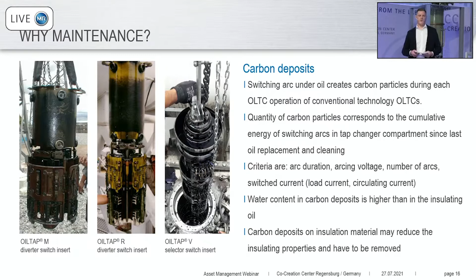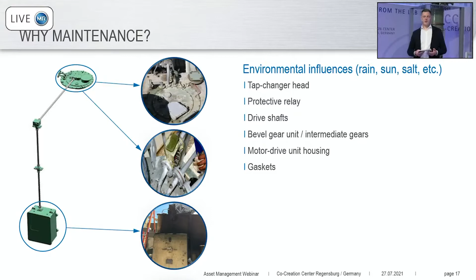Then, of course, we have some environmental influences on the tap changer cover, on the protective relay, drive shaft arrangement, the bevel gear unit, the motor drive unit housing. All this, what is outside on the transformer, you may for sure know it, is exposed to rain, thunderstorms, sun. Here in Germany we also have hail, or if it's installed close to the sea, we have also the effect from the salt water, which affects the equipment as well. So it should be cleaned, regularly checked, maintained, lubricated, so that we ensure everything is in good condition.